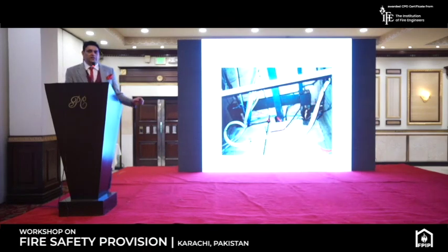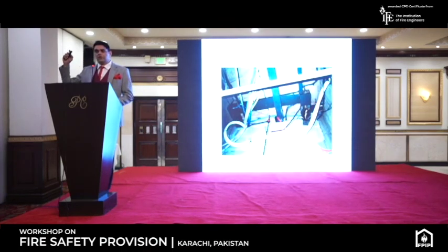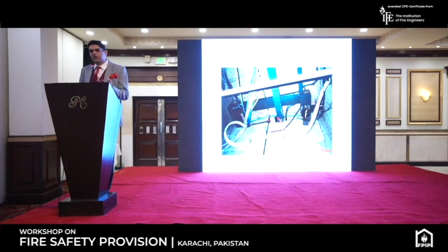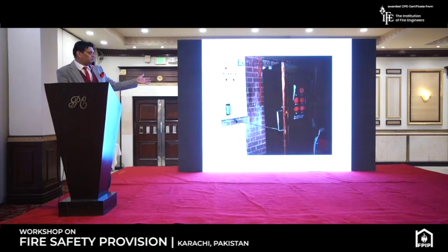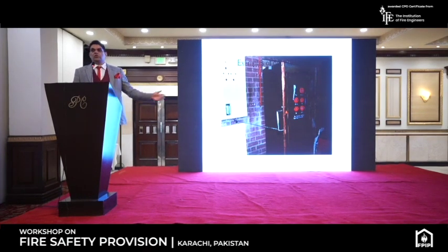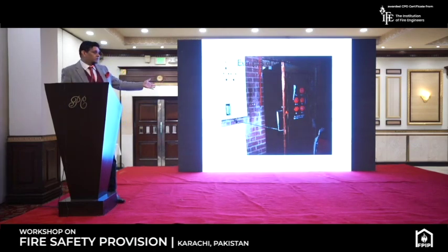This is the main area we have seen: normally above our floor we put the false ceiling, and beside the false ceiling, all this kind of wiring is there. So it has to be closed, shut, stopped. Normally we have a fire door, but we just leave it like this, always accessible. It's a requirement of the legislation that a fire door must be closed all the time. That's why there is a fire door closer on the exit door.